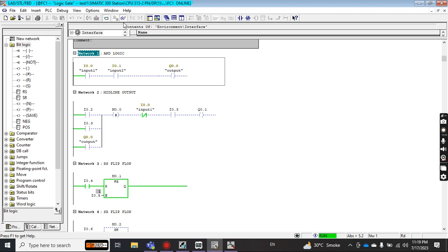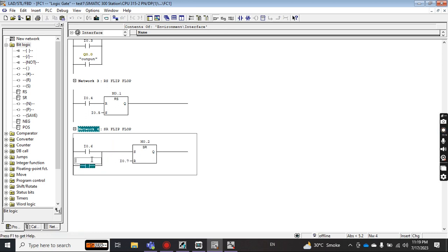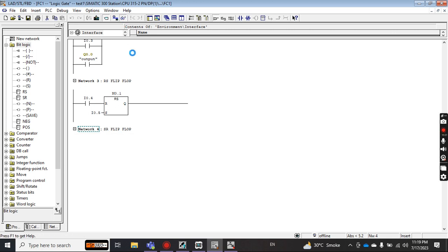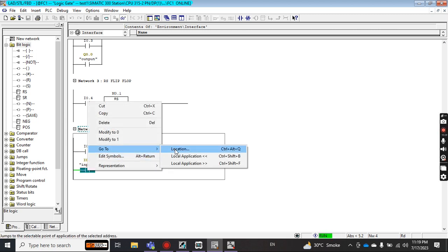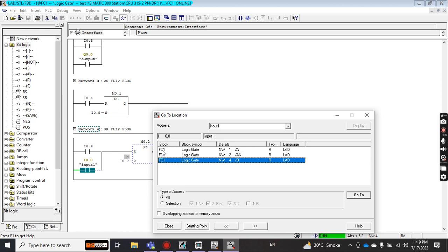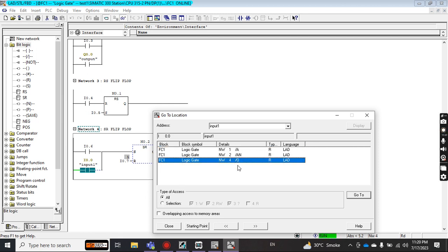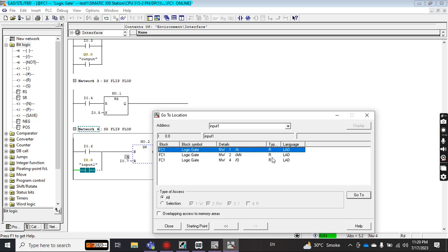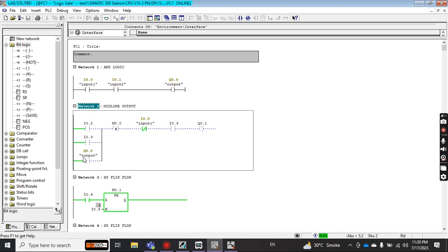Let me add the same input I0.0 again at the end, save, and go online. Now using 'Go to Location,' it shows the address is used three times: in FC1 Network 1, Network 2, and Network 4. It also tells you how each instance is being used — as a Read or Write. So R means it is being read. Clicking on any entry navigates you directly to that network.